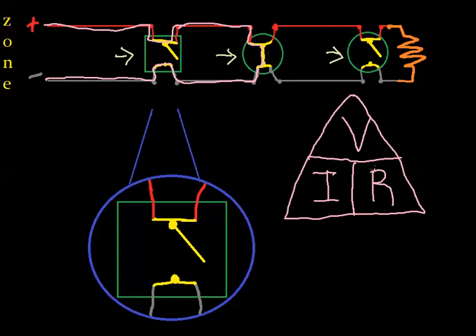If you want to know resistance, it's voltage divided by current. If you want to know voltage, it's current times resistance. So that's easy enough. If let's say we have 24 volts here. And let's say our end-line resistor is 6,000 Ohms. It's a little Omega sign for Ohms. Sorry, I'm almost off the page there. Or 6K, 6 kilo Ohms is how that's normally written.